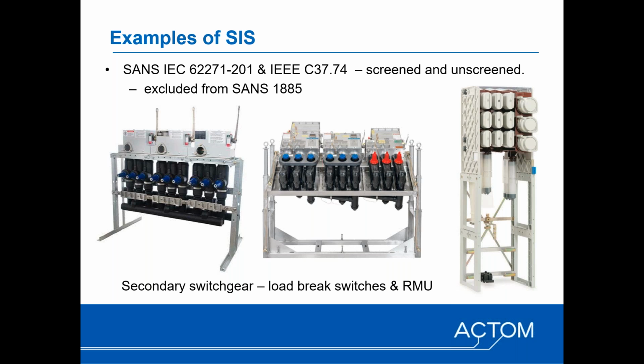So some examples of solid dielectric switchgear covered by, in this case, we've got examples of -201, so that's what we call insulation enclosed. It does not have a metal enclosure around the high voltage conducting parts. So the two examples on the left and in the middle are common in the US. Those are effectively load break switch ring main units. And each pole you can see there consists of a solid embedded pole, which has got an earth-screened layer on the outside. And those are covered by the American IEEE C37-74 standard, and have been used for many years.